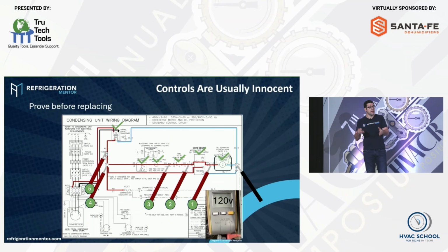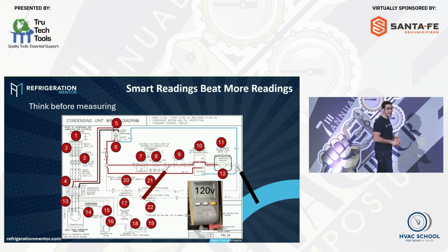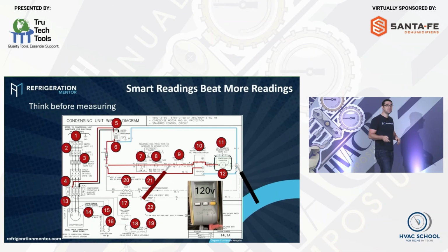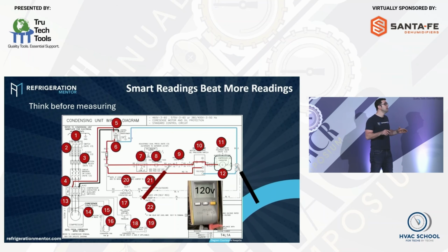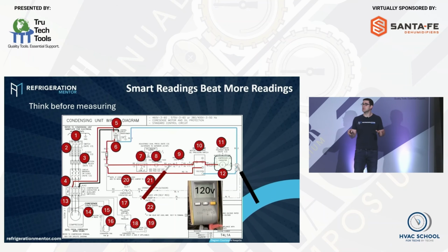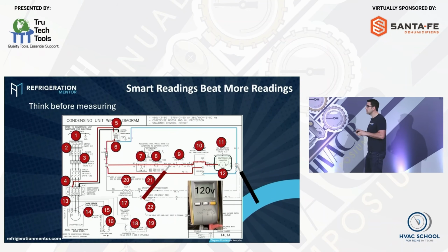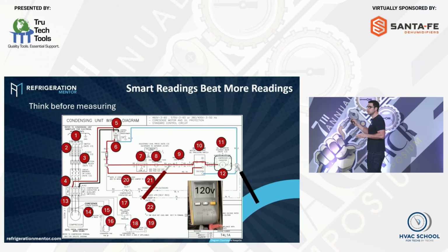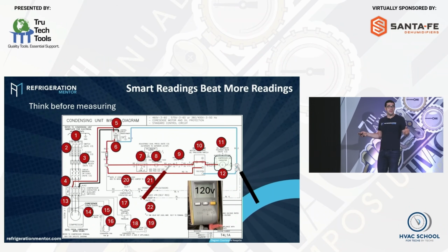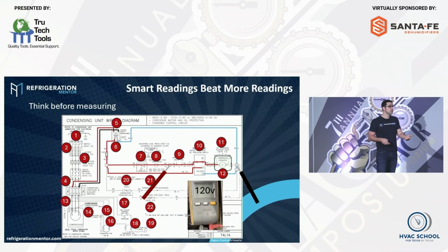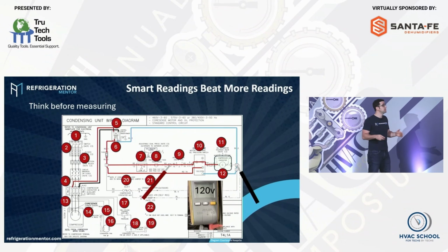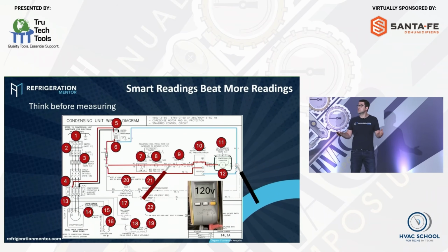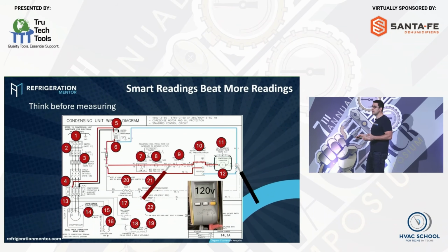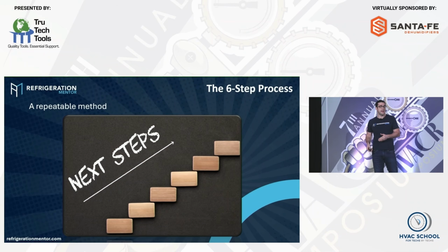The steps on using it. Follow the path. Okay, smart readings beat more readings. There are only so many tests in an electrical circuit. It doesn't matter what unit you're on. I don't care what you say. It could be a big industrial system or a little small one. There's only so many tests. It could be like this one here. You got 22. There's only 22 checks that you can do. And a big system could be 10,000 checks, but there's only so many. And if you know all of those checks that you need to do, that's going to speed up your troubleshooting time. It's understanding that logic before.